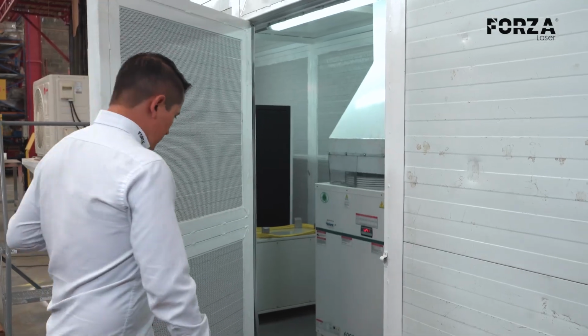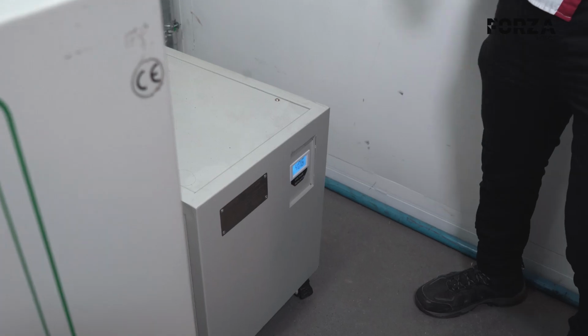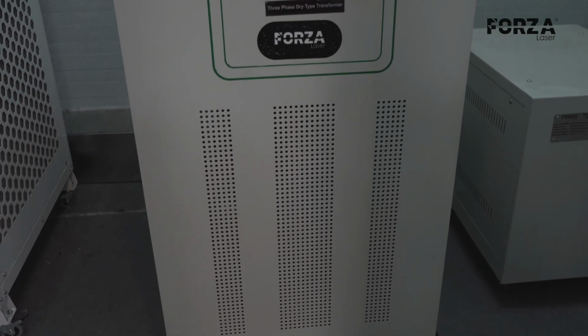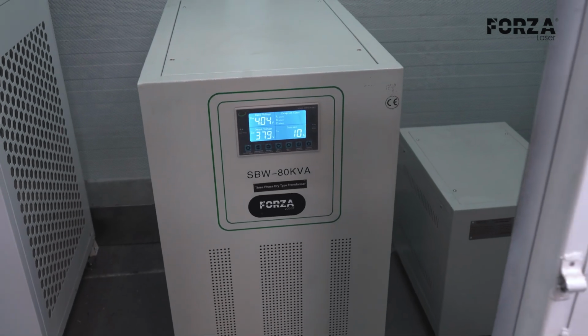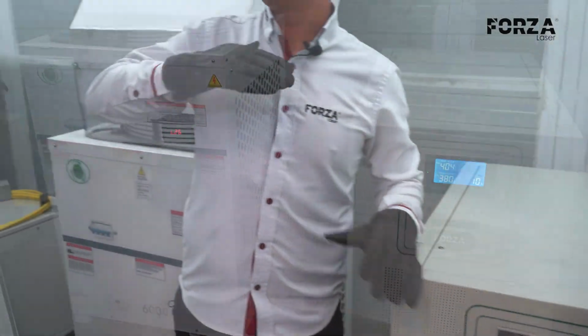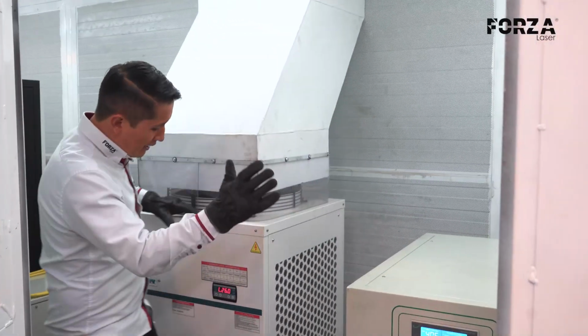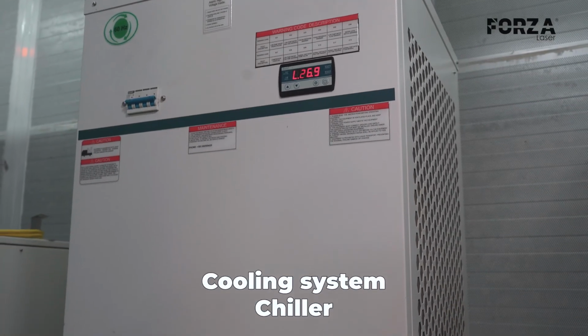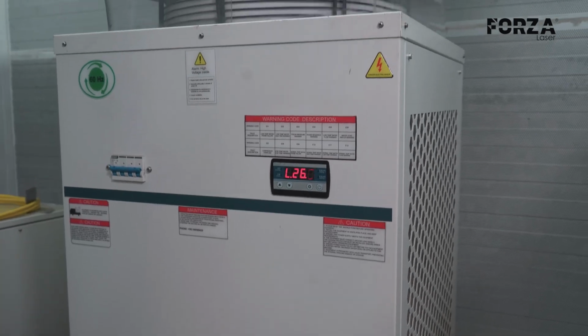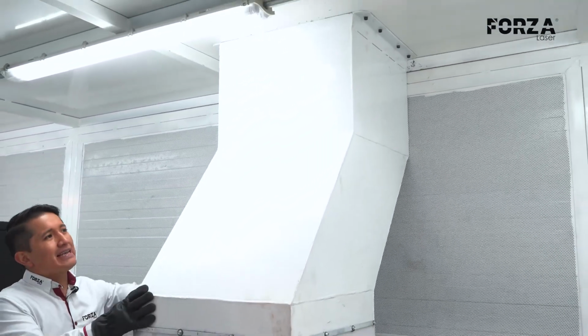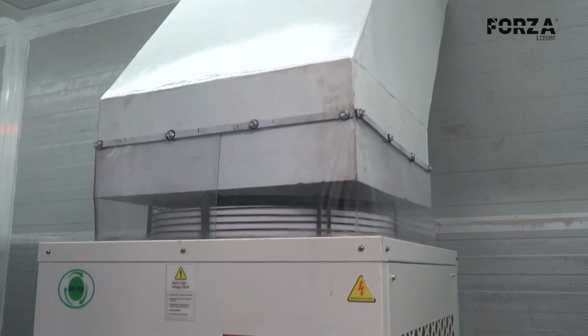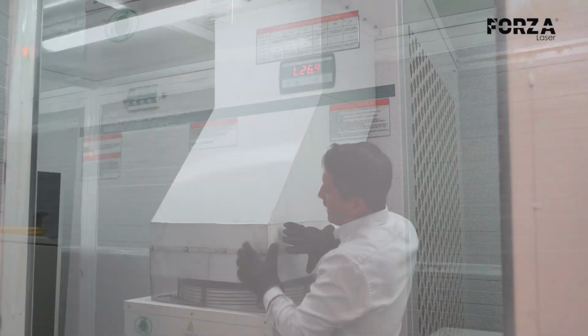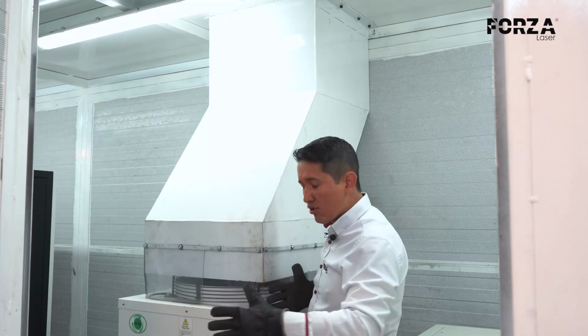In this environment, we have the main peripherals, starting with the regulation system, the stabilization system. Well, this one maintains a constant voltage to the equipment so that when there is an over voltage or a drop in voltage, the equipment is not at risk and always maintains stability in the electrical supply. This is super important since the laser is very susceptible to voltage changes. Over here we have the cooling system, which is a chiller. Basically, it recirculates water for both the laser source over here and the head. It has this duct which has been constructed to the outside because hot air comes out from here. If this duct did not exist, the air conditioning would have to work excessively, which is why this duct is installed, so that all the hot air generated by the water cooling can exit through this duct.